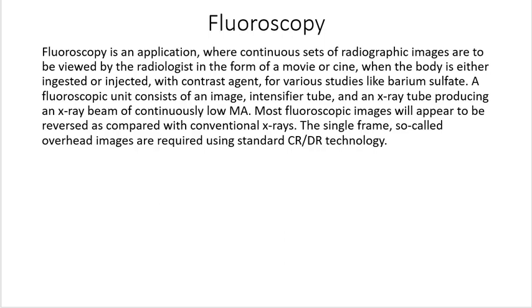So in a fluoro exam, they're going to use a fluoro unit which has an X-ray tube that produces the X-rays, but they use a very low dose. So they need an image intensifier tube to make the image bright enough to see. And you look at a monitor and watch the fluoroscopy as they're drinking or they're breathing. You want to be able to see the motion in a video, whereas in most X-rays we want to stop all the motion. And then sometimes afterwards they'll take a still frame.